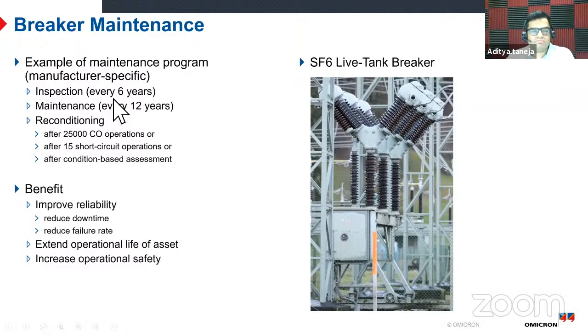And the idea is not to do a very detailed test every year, because that is just wastage of time, effort and resources. So the idea is that whenever we do the testing, it should be enough to increase the time intervals between subsequent tests, so that your system does not get shut down every time. You don't have to take it out and do all this extra effort required to take a shutdown and get a permission to do testing. So that's an objective which we want to have.